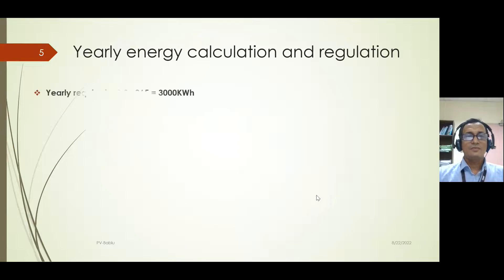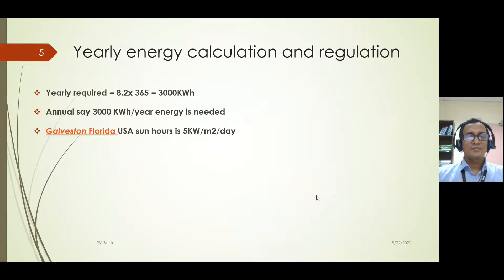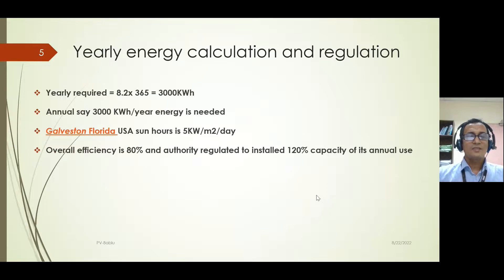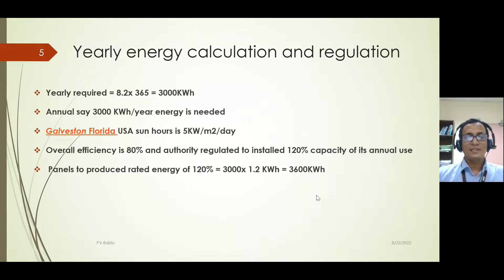The yearly consumption is 8.2 kWh multiplied by 365, which is around 3000 kWh. The local insolation is 5 kWh per meter square per day. The system overall efficiency is considered at 80%, and local regulation for installation allows only 120% capacity to be installed supported by the grid-connected system. So 120% of 3000 kWh equals 3600 kWh.